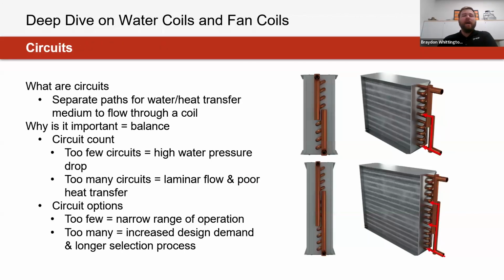In terms of circuits, they are essentially the number of paths of coil going through the coil itself. Why they're important, especially when looking at the performance of the coil, is that as we increase the number of circuits, say to a 19 circuit or 17 circuit coil, adding too many in a lot of cases could have some detriment on your heat transfer. More importantly, that laminar flow range we were talking about earlier might get less predictable in performance, as the fluid is distributed into so many different fluid paths that it gets below that 0.3 or 0.6 GPM per circuit target. But if we decrease the number of fluid paths, it adds a higher fluid pressure drop on our system too.